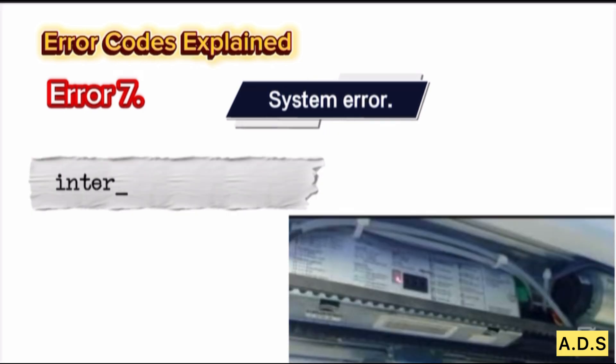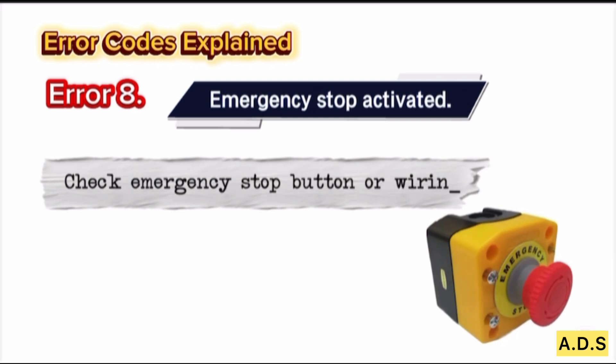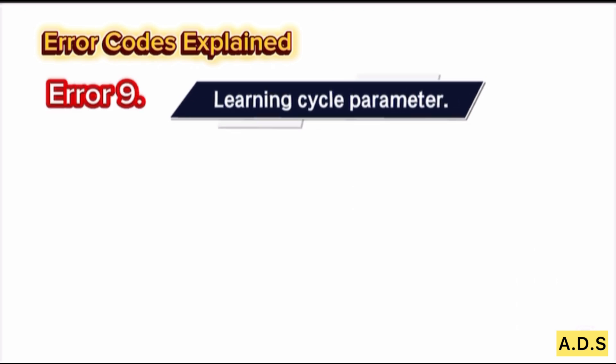Error 7: System error — internal control board issue. Error 8: Emergency stop activated — check the emergency stop button or wiring. Error 9: Learning cycle parameter error — a relearn cycle is needed.